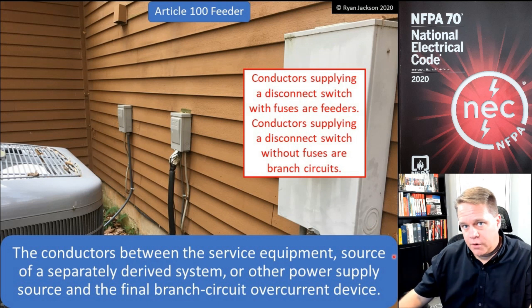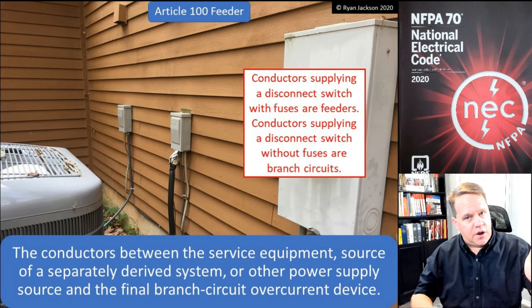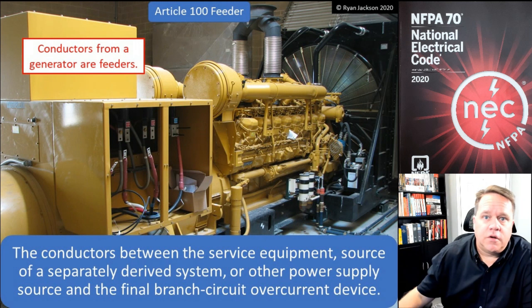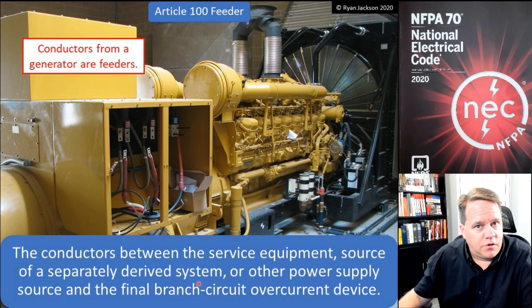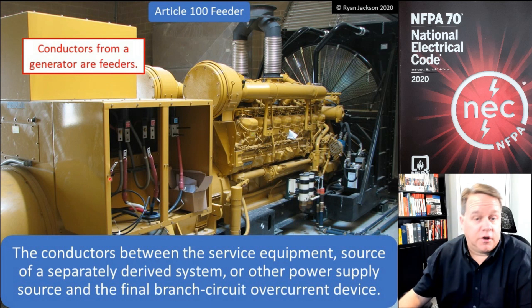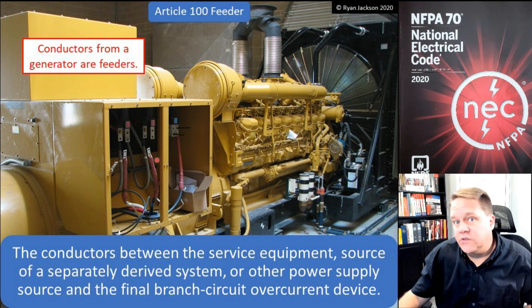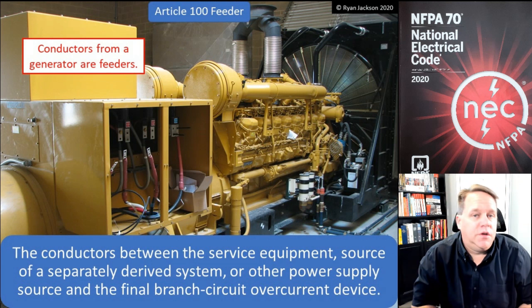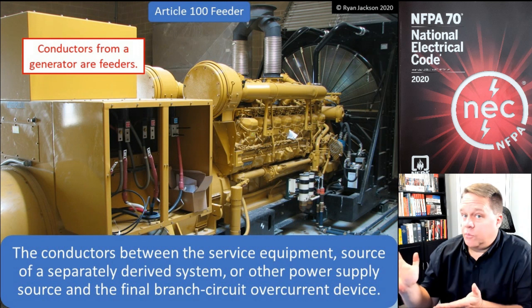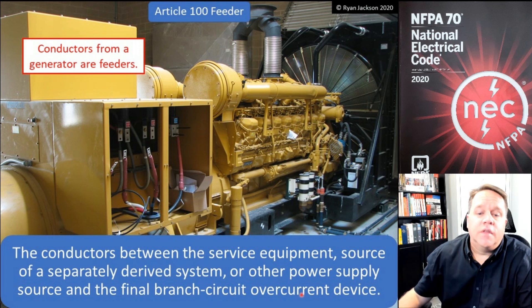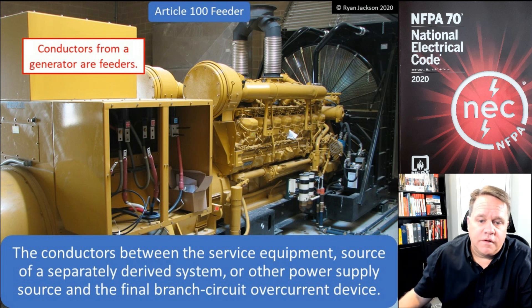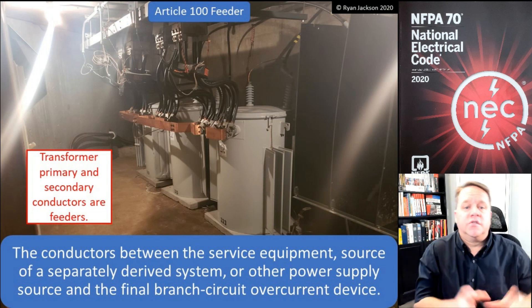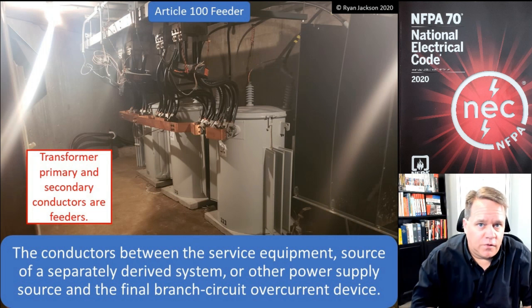If there is a breaker or fuse in the disconnect, then the branch circuit starts at the disconnect and ends at the unit, and the feeder circuit runs from the panel breaker to the fused disconnect. If it's not fused, there's no feeder — just a branch circuit. Feeders can also start at the source of a separately derived system. For example, conductors leaving a generator that has no breaker or fuse: they're not service conductors (those can only come from a utility), they're not branch circuits (didn't start at a breaker or fuse), so they would be feeder circuits.